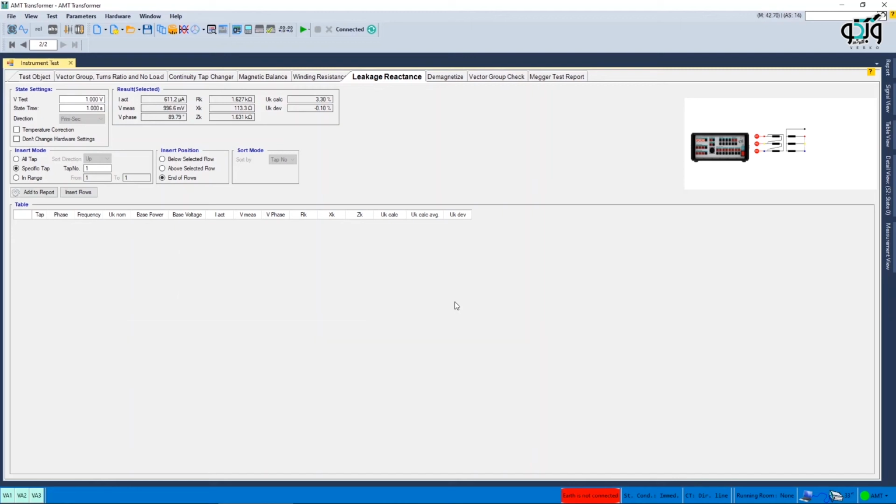It is necessary to observe some points in this test. To short circuit the secondary side, the cable size is calculated. Cable size or short circuit busbar on the secondary side are obtained using an example. Suppose there is a transformer with 7.5 megavolt ampere of nominal power, 33 to 11 kilovolt conversion ratio with DYN11 vector group and a 10% short circuit voltage.